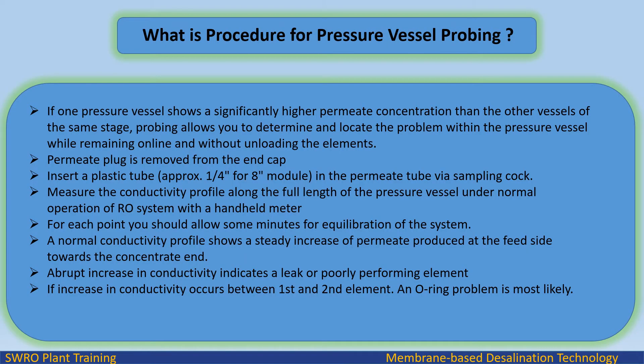What is the procedure for pressure vessel probing? If one pressure vessel shows a significantly higher permeate concentration than the other vessels of the same stage, probing allows you to determine and locate the problem within the pressure vessel while remaining online and without unloading the elements.